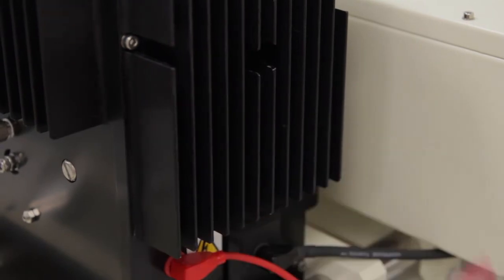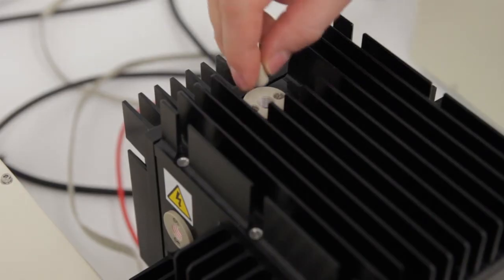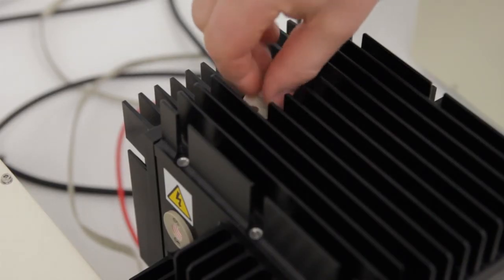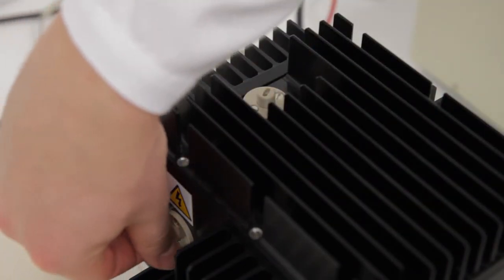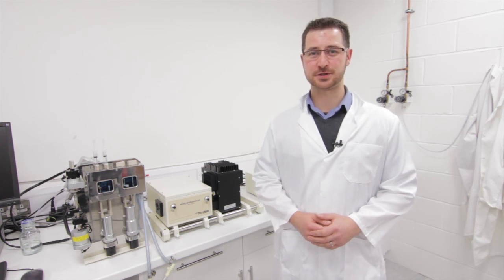Tighten the locking screw to secure the lamp's position. Finally, screw the beige plastic caps back into the adjustment ports. Your stop-flow spectrophotometer is now ready for use. If you have any questions, please contact our customer support team.